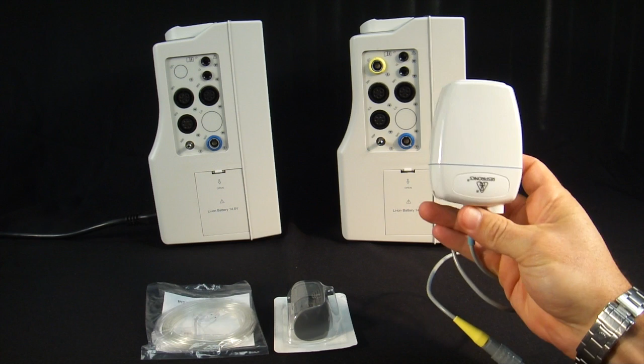If you do look on the side of this machine, you'll notice that the CO2 port is closed. Traditionally, we've shipped with an open CO2 port, and I'll show you on the side of this machine. That open CO2 port features a LEMO connection that adapts to the Philips Respironics LoFlo module. This has been our CO2 solution up to this point. All the machines have come with that open port, and you can add this at any point, or your customer can add this at any point.